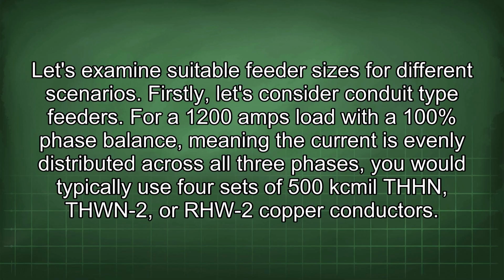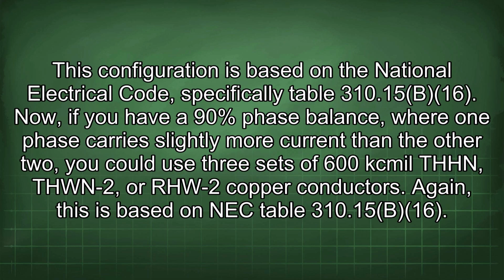Firstly, let's consider conduit-type feeders. For a 1200 amps load with a 100% phase balance, meaning the current is evenly distributed across all three phases, you would typically use 4 sets of 500 kcmil THHN, THWN-2, or RHW-2 copper conductors. This configuration is based on the National Electrical Code, specifically Table 310.15(B)(16).